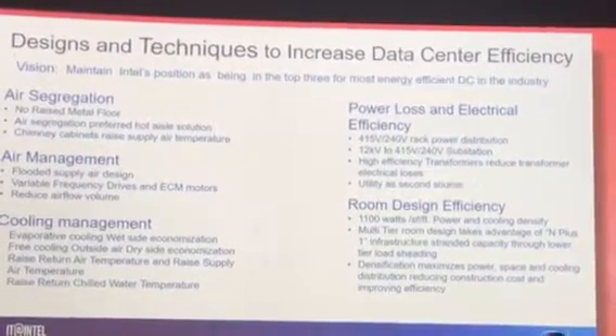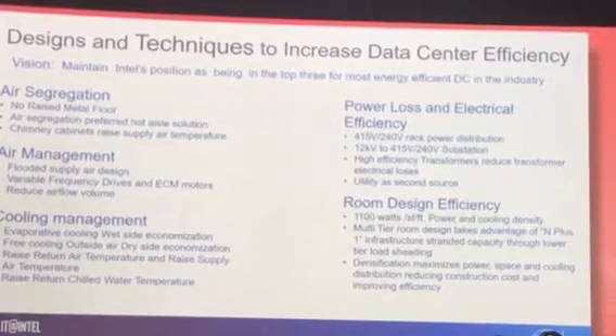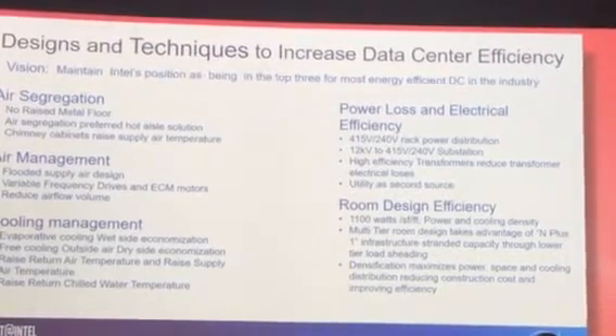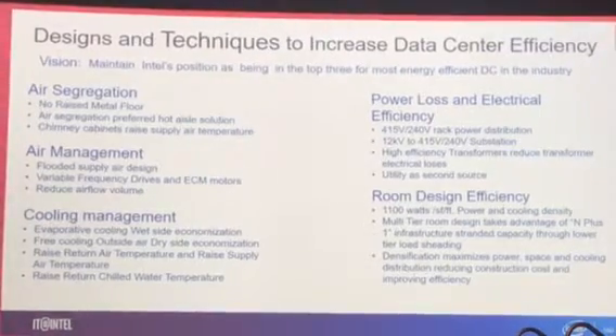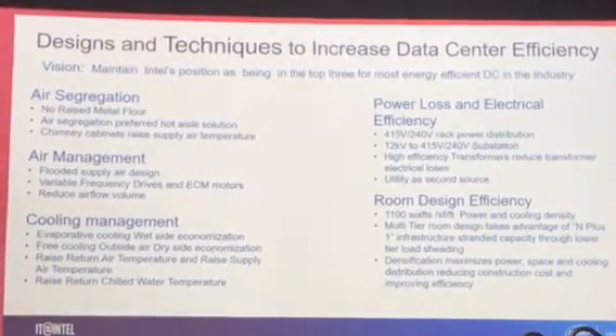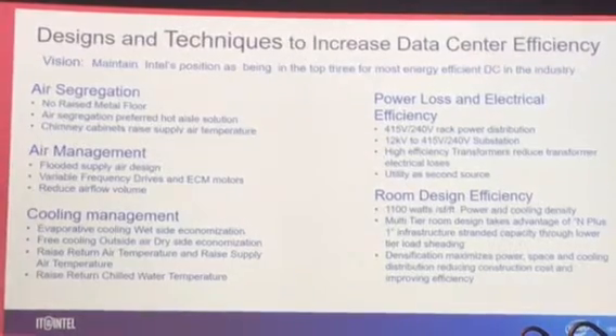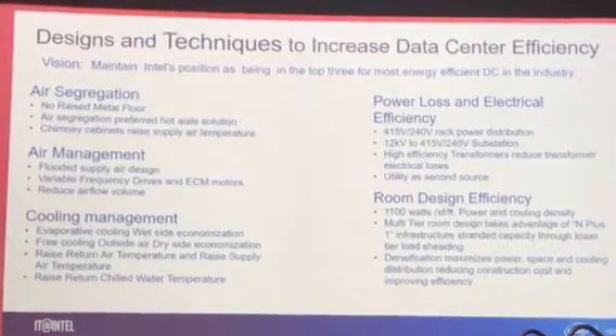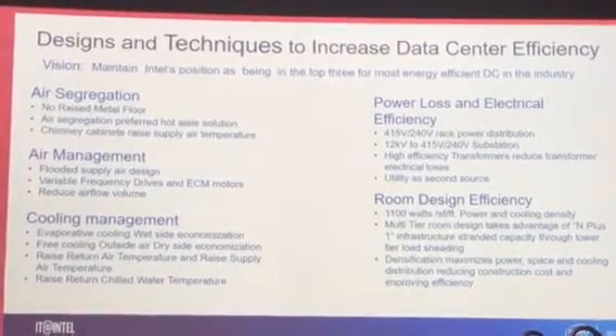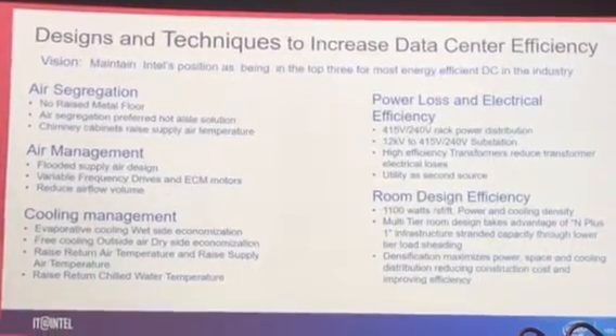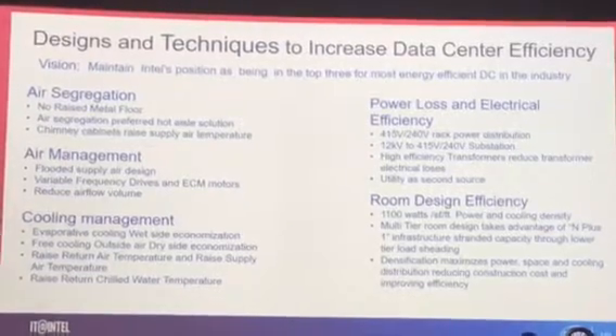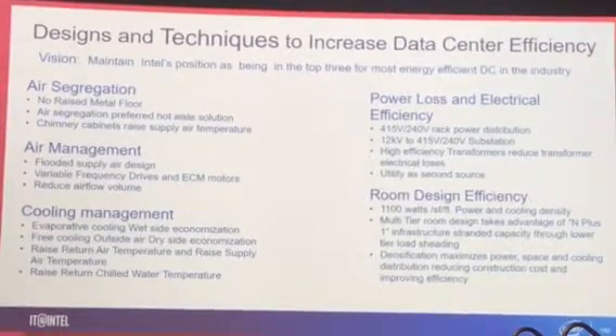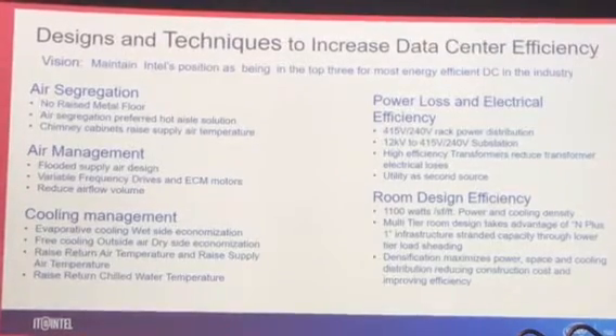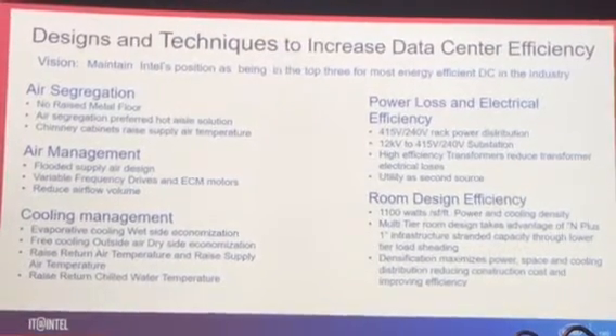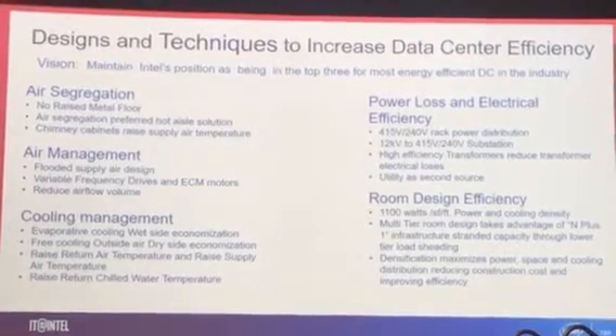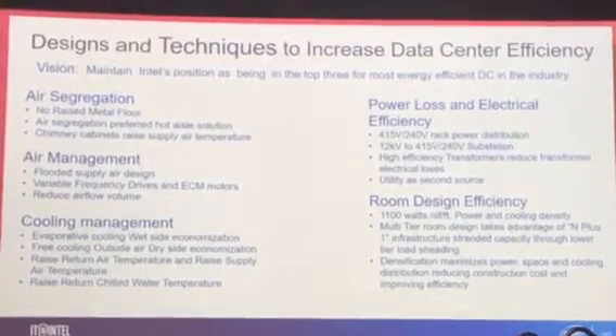So what we learned from this process, where we started 5 years ago, on how to improve efficiency, we used many things. The air segregation, you know, to improve efficiency. We know that the air segregation is important. You need to make sure you have segregation between hot and cold aisle, no leaks, or reduce the leaks as much as you can. Chimney cabinets also could work. And also, like I said, no raised metal floor. From the air management, flooded supply air design, we use variable frequency drive or ECM motors to change the speed with just a Modbus signal.